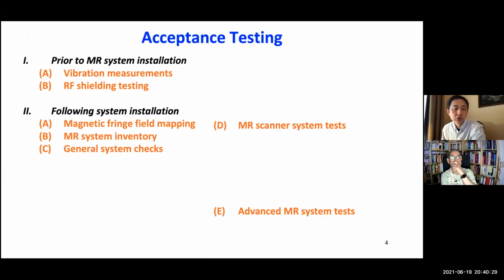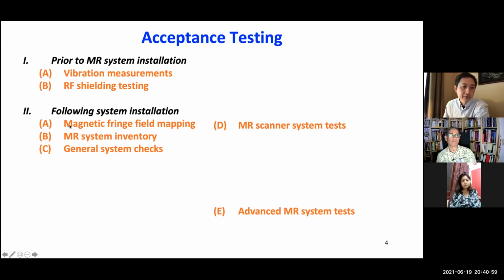So let's give a broader scope about acceptance testing of an MRI scanner. When we receive a new MRI scanner, what do we need to do? Actually, what we need to do starts before the MRI scanner arrives. Before the MRI installation, we need to have a vibration measurement and RF shielding measurement. That's the MRI room shielding. And then after the installation, there are 5 components of the testing. The magnetic fringe field mapping, I will give some examples later. And of course, inventory is needed for all the new equipment, then general system checks. And then the MRI scanner system test. This part is what we usually call system testing or QC testing. Also, we do this annually. And then advanced MRI system testing. If we have advanced applications, we will do this part.